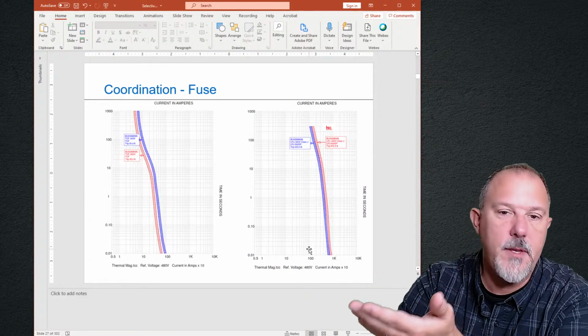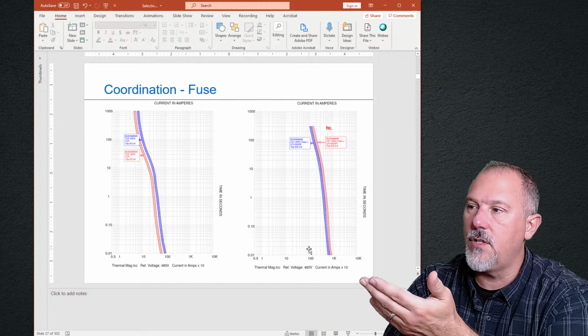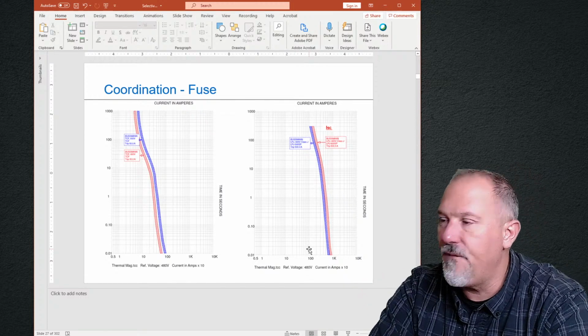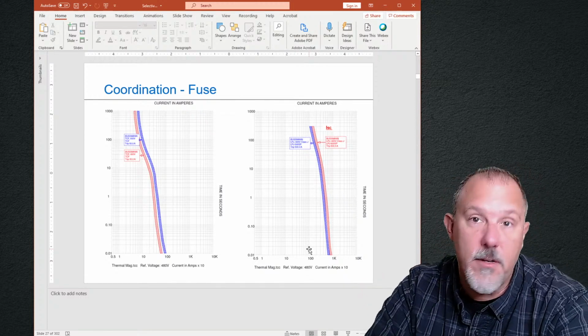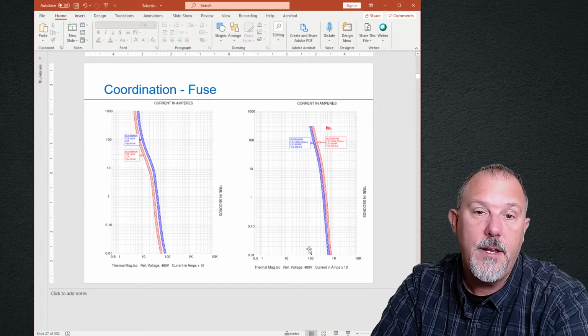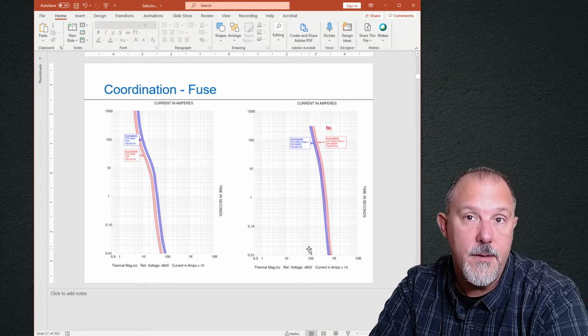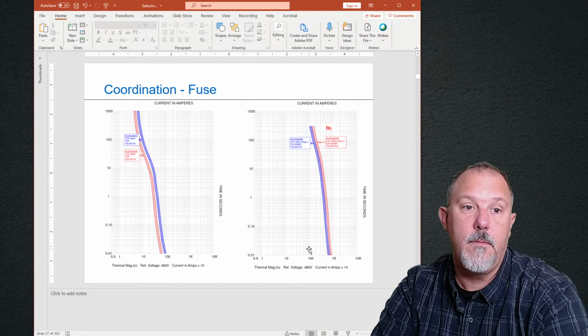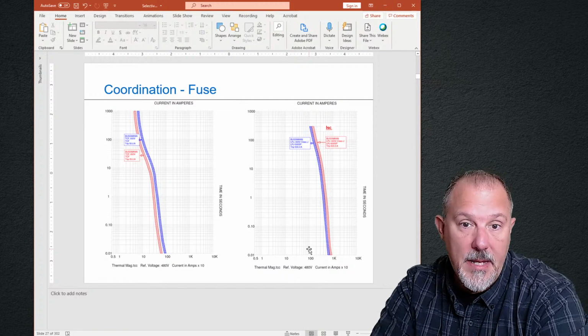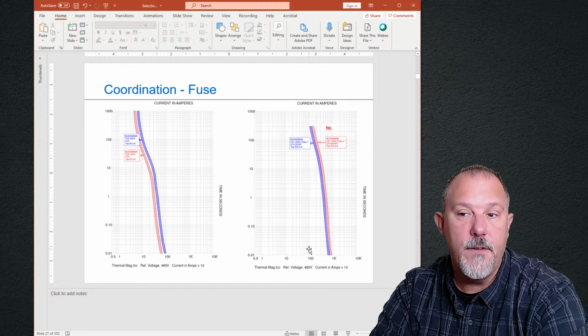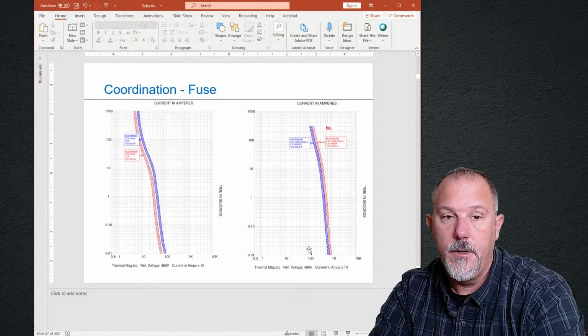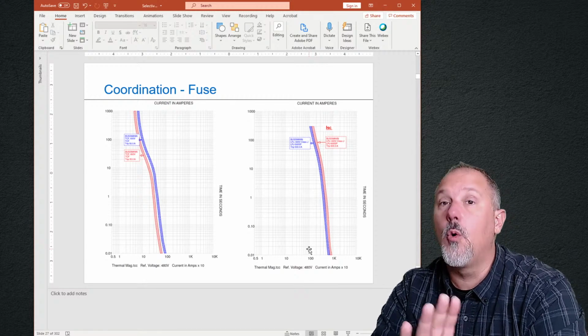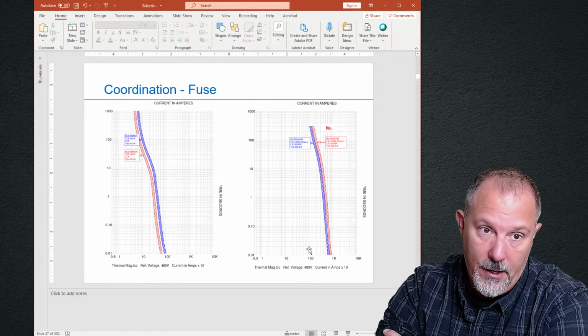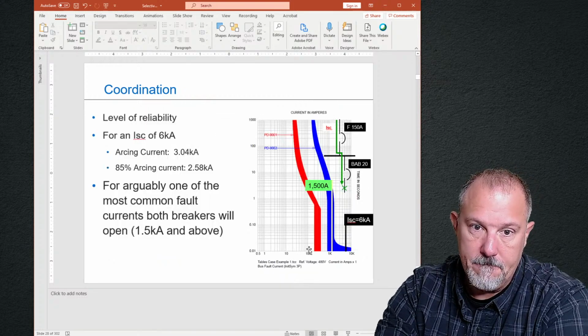And I could do the same thing with fuses. I could put a 600 amp fuse upstream of a 500 amp fuse. I would guarantee they're both going to open, but I would meet the requirements of 240 of selective coordination for Article 517.